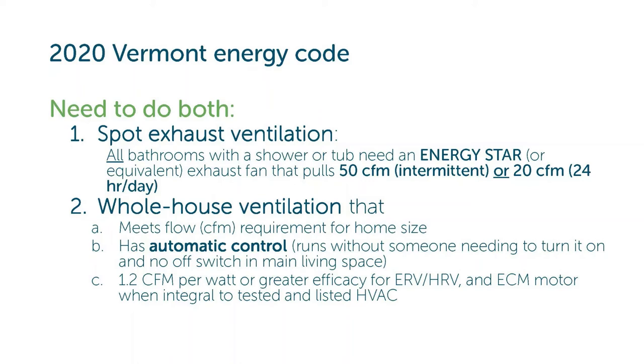And number 2. Whole house ventilation that meets a specified airflow based on the home size and has automatic controls not requiring occupant intervention. ERVs and HRVs used for whole house ventilation must meet or exceed 1.2 CFM per watt efficacy. If the system relies on the HVAC system for distribution, then that HVAC system must have an electronically commutated motor, or ECM.